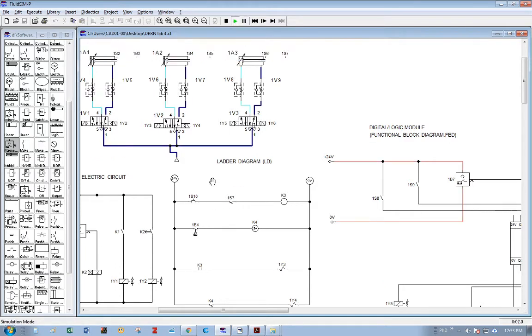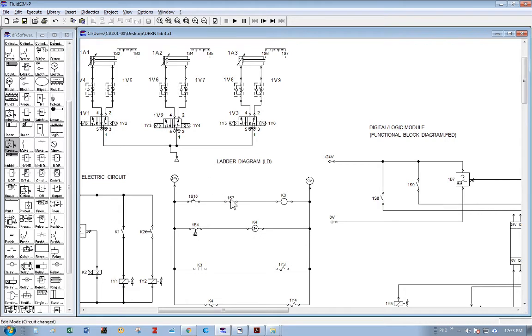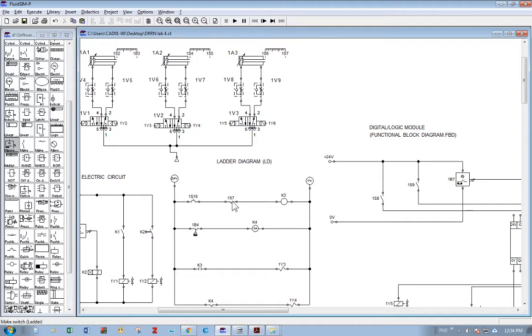Moving on to the ladder diagram. When we push the start button, nothing happens — the circuit is open. 1S7 is referring to a limit switch that is not connected to the pneumatic circuit we are concerned with. I need to relabel it: it should be 1S4. Connecting two contacts in series resembles the AND logic, and we are interested in connecting the start button with the first limit switch, so this should be 1S4.